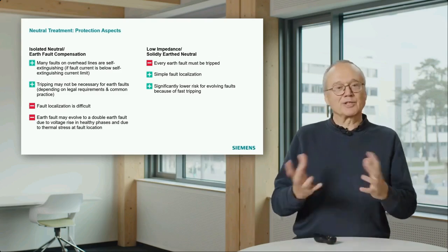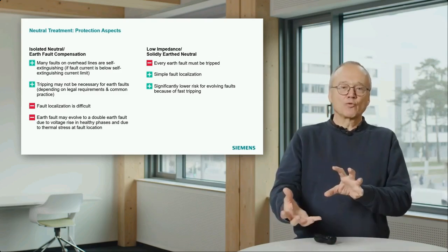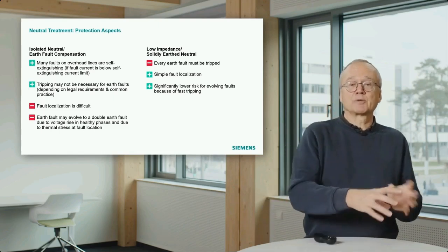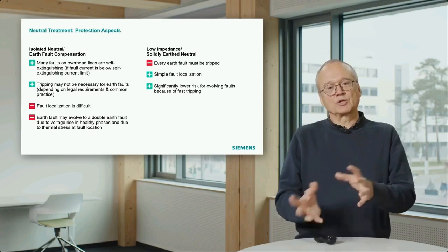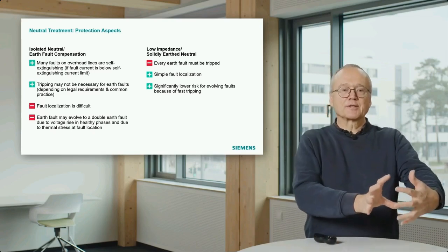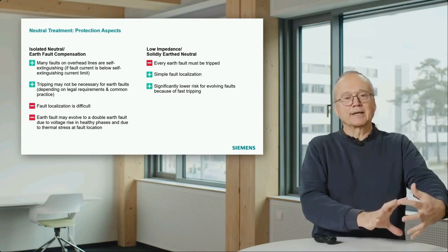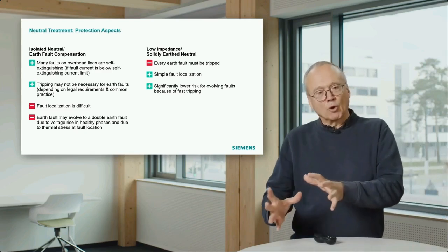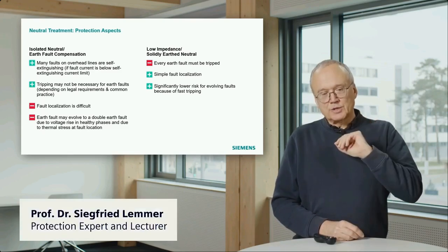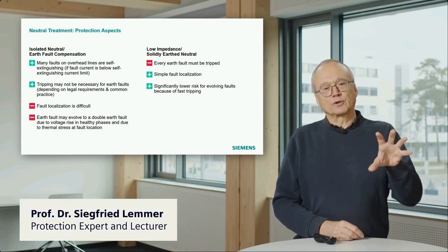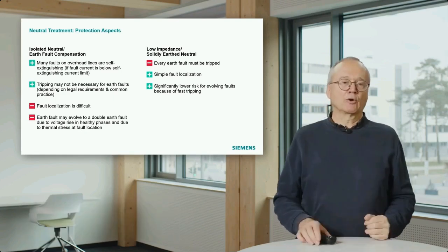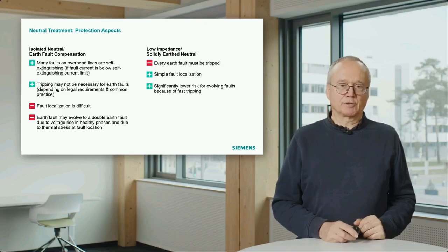And some countries are even sometimes moving, or some utilities are sometimes moving from one concept to the other because they see advantages there. For instance, if you convert a system from a pure overhead line system more into cable system, then you lose some advantages of earth fault compensation. So it may make sense to think about the Starpoint treatment.